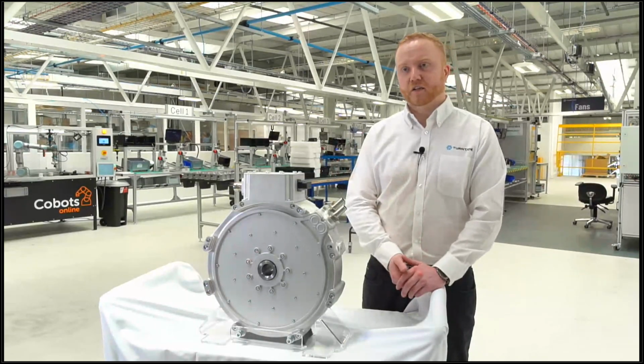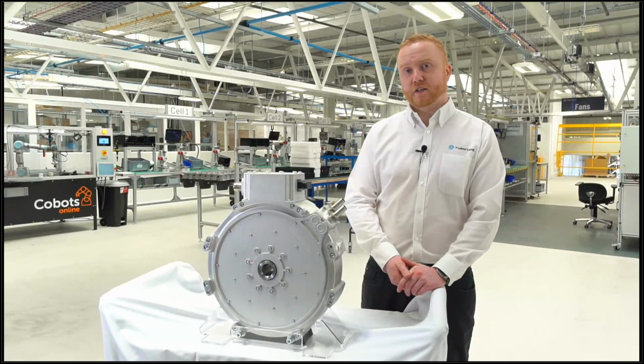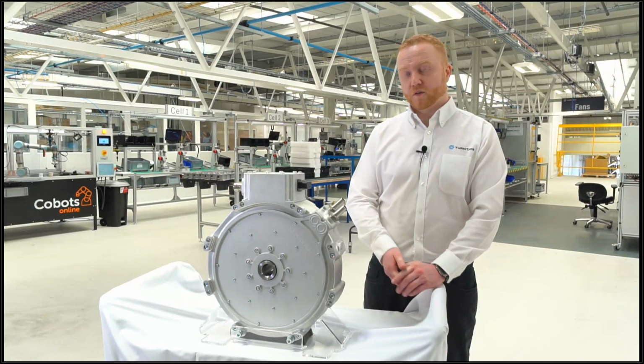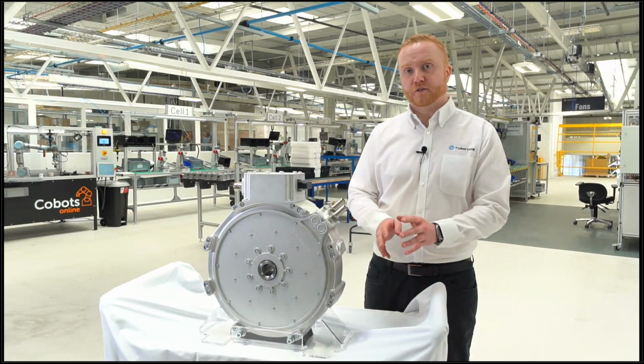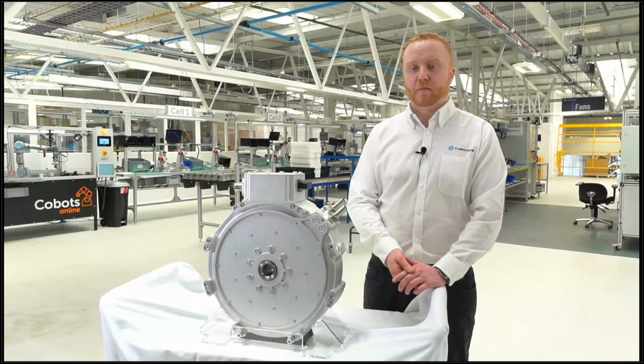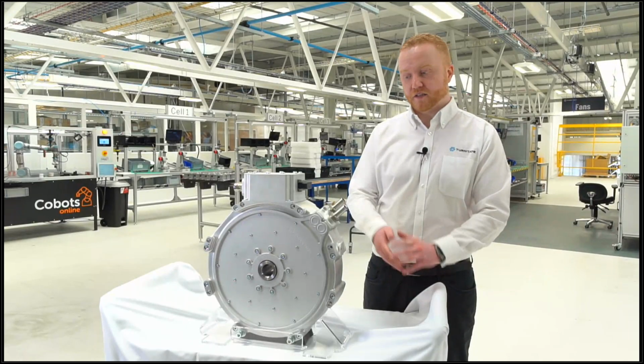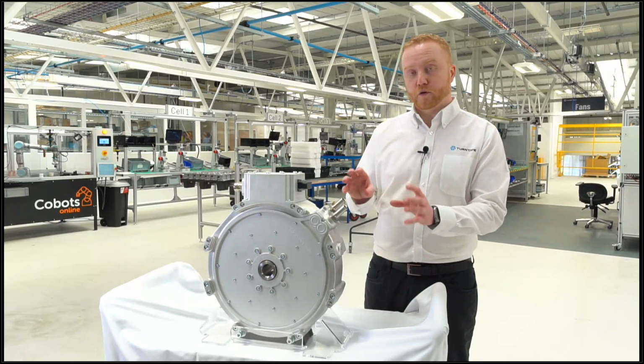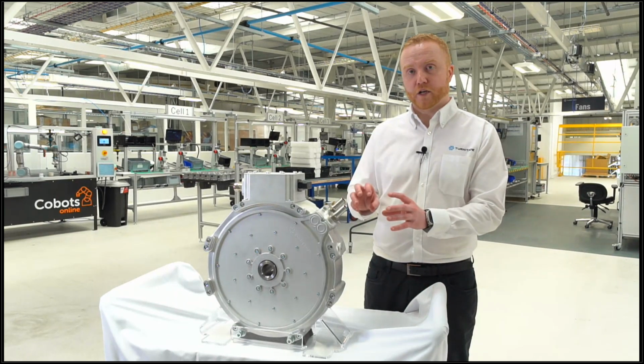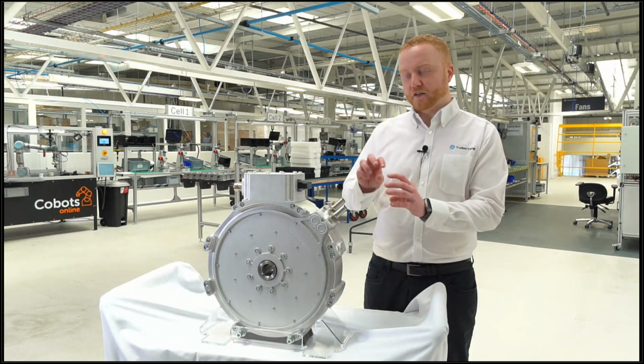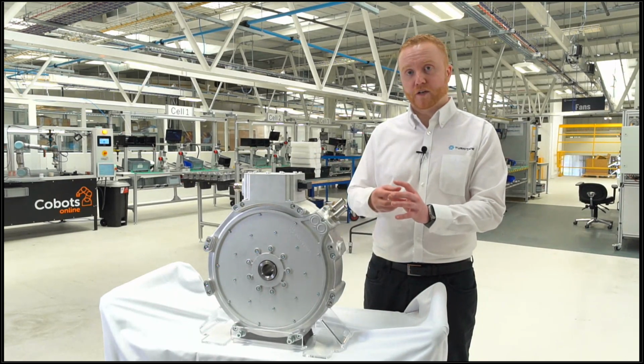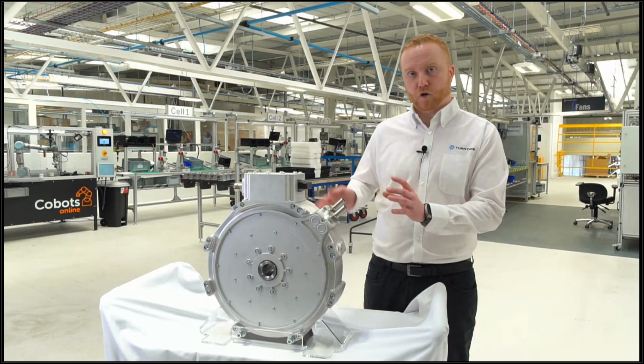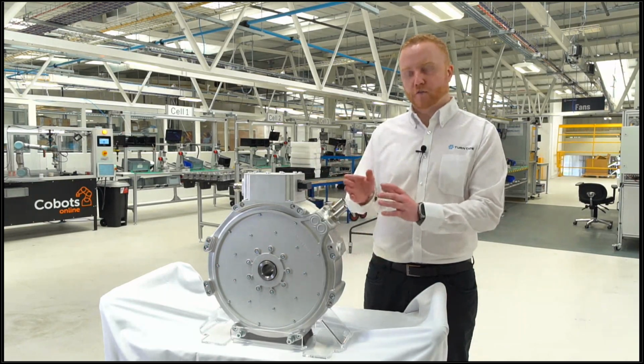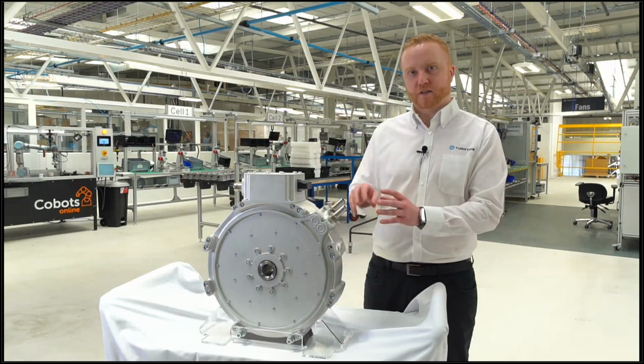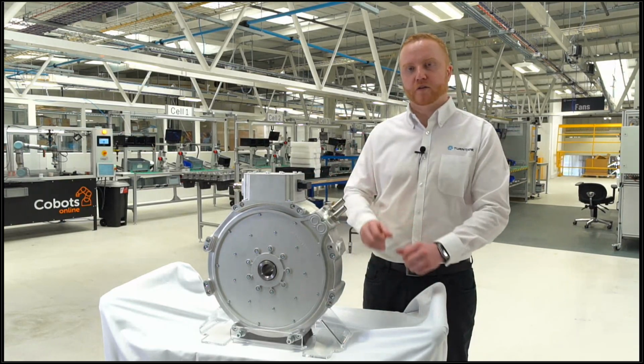The reason we selected that location is due to testing we did with samples run at different duty points and cooling temperatures. We had test samples with PT100s embedded at different locations around the circumference of the windings, at different clock positions relative to the top box, and at different radial positions—inner windings, outer windings, and different points in the slot.